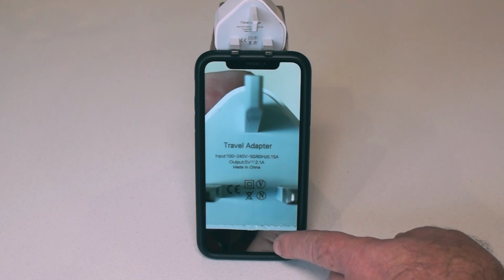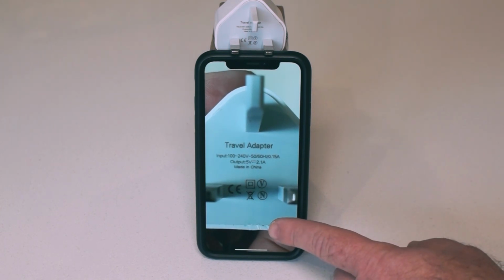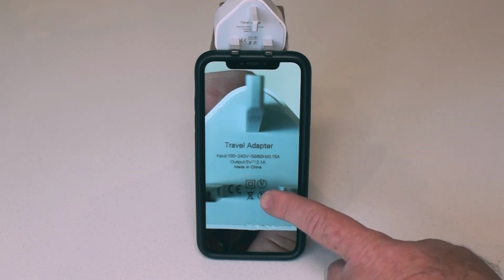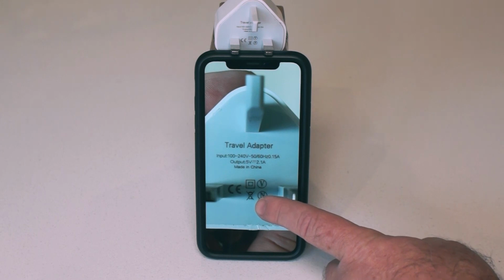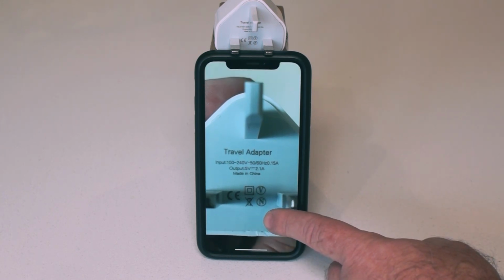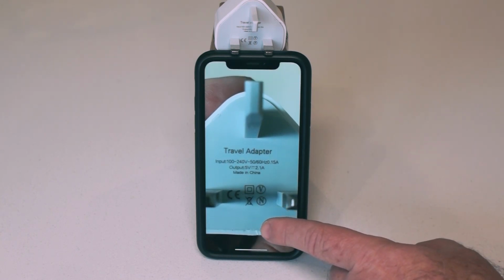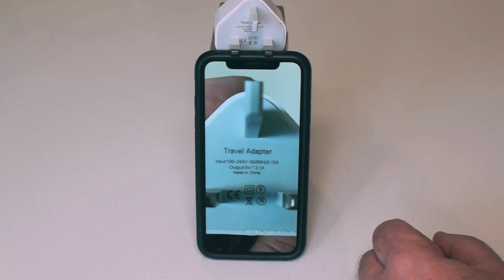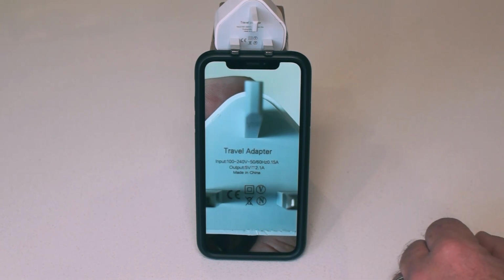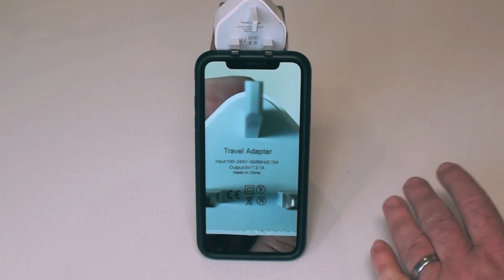Here's the first of our USB chargers. I've taken a picture and enlarged it to make it easier to see. It has 100 to 240 volts, 50-60 hertz, 0.15 amps, an output rating, the double insulated symbol, and the crossed wheelie bin symbol. These are all good things. What it doesn't have is manufacturer's name, identification, trademark, and a model number, which is required by the standard. So not bad, but still a fail.